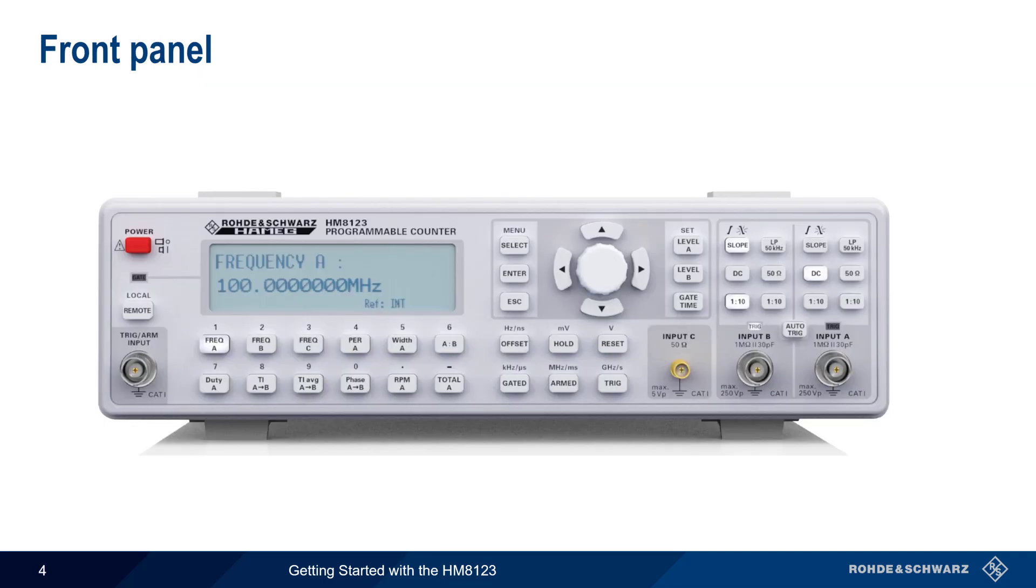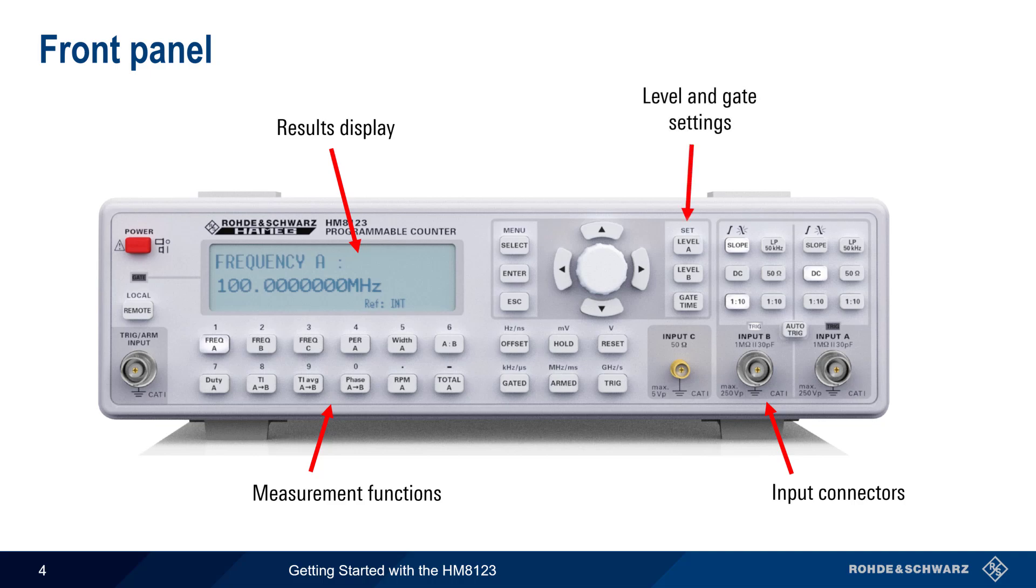Let's start by looking at the most important front panel buttons and connectors. The three input connectors are on the bottom right, and measurement results are displayed on the top left, just above the measurement function keys. The keys for both level and gate settings, as well as for input controls such as attenuation, filtering, and coupling, are found above the input connectors. The measurement controls can be used to pause or reset measurements, and they're also used with the front panel trigger-in connector.